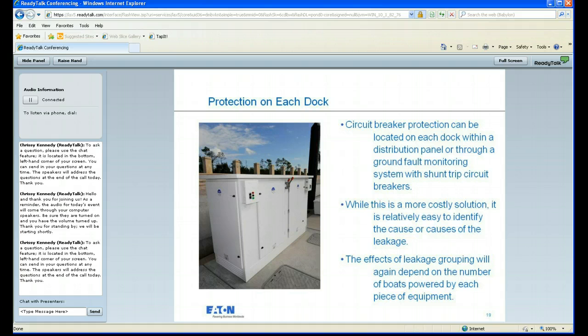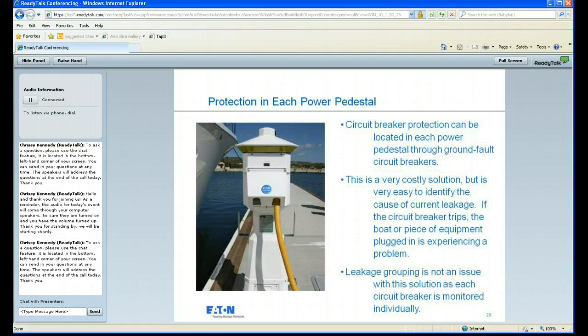Depending on the number of circuit breakers you have controlling a certain number of boats, it may be to the point where you track down the circuit that's causing the leakage or causing the alarm to go off, and boat by boat turn the power back on to these vessels. Whichever vessel causes the alarm to trip or the reading to spike, you know you've identified a cause or causes of the current entering the water. Again, the effects of current leakage on this system will also depend on the number of boats being powered by that piece of equipment. So knowing the number of units you have on a given circuit or on a given detection device is important to understand how to identify the units that are causing the problems.